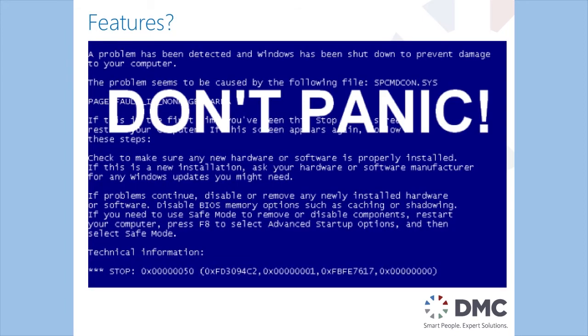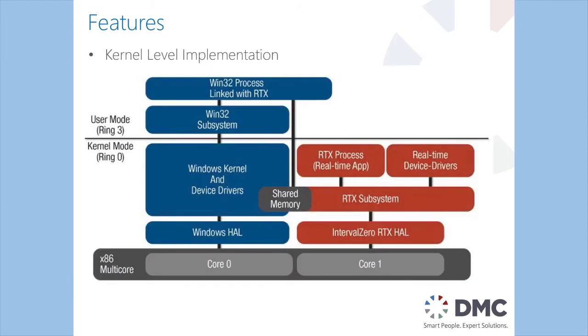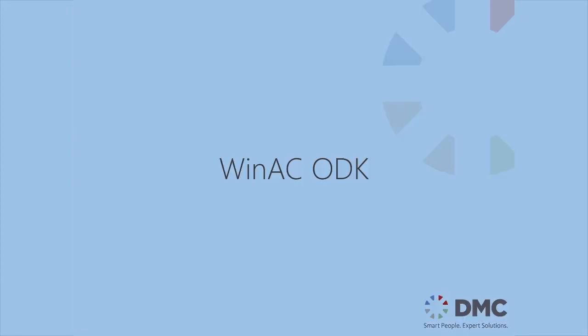And I don't want you to panic. Most people do when you say Windows in an industrial setting. But the way this is implemented is the PLC portion is linked in below the Windows operating system. It's implemented at the kernel level in Windows. This means that if your Windows operating system crashes your PLC is still up and running and you can recover from this situation gracefully.